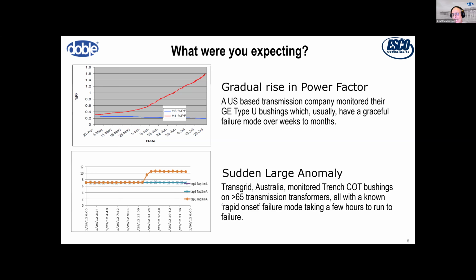We know you can't just broad-brush how one asset from one manufacturer will perform versus another. In some cases we see a gradual rise in power factor. This was a typical failure mode of the GE type U bushing, discussed a lot in the late 20th century and into the early 21st, where they would slowly, gradually get worse until they failed. But then we have situations, like a Trench COT bushing, where one suddenly spikes up, putting it in a very dangerous condition. Your reaction to each of these cases would be different.